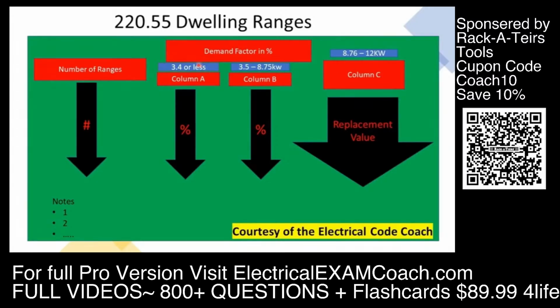Starting on the left-hand side in column A, this is when your individual range falls at 3.4 or less kW. Column B is when the individual range itself falls between 3.5 and 8 3/4. Then column C is when our ranges are 8.76 through 12 kW. Then in the bottom left-hand corner of the table, you're going to see some notes. That's when we have a situation that doesn't fit into the normal table, and we're going to take it piece by piece. Let's get to it.